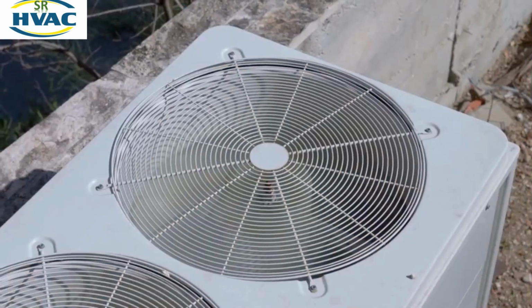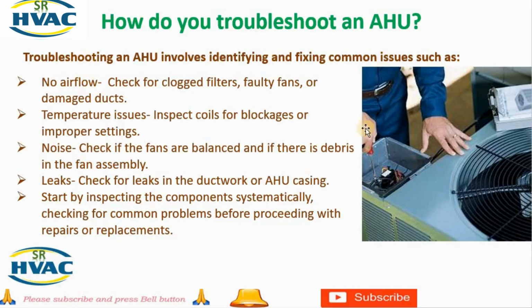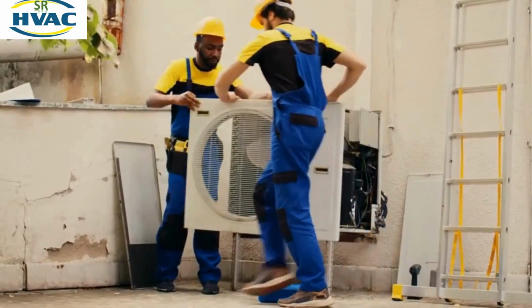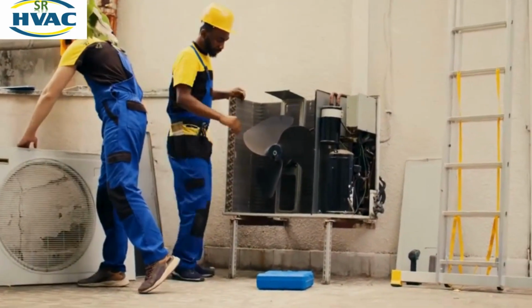When it comes to troubleshooting, you need to know the steps to identify problems. Start by checking for common issues like no airflow. Check for clogged filters, faulty fans, or damaged ducts. Temperature issues. Inspect coils for blockages or improper settings. Noise. Check if the fans are balanced and if there is debris in the fan assembly. Leaks. Check for leaks in the ductwork or AHU casing. Start by inspecting the component systematically, checking for common problems before proceeding with repairs or replacements. Make sure to explain your systematic approach and knowledge of how to handle various issues.